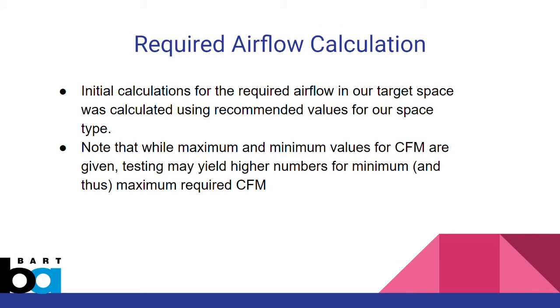For our required airflow calculation, our required airflow in our target space was calculated using recommended values for our space type. These recommended values are defined by ASHRAE and other online resources based on our space type. Note that while the maximum and minimum values for CFM are given on the next slide, it may be that from testing, we may find that higher numbers of minimum and maximum required CFM are actually needed to remove the amount of heat that we are anticipating.